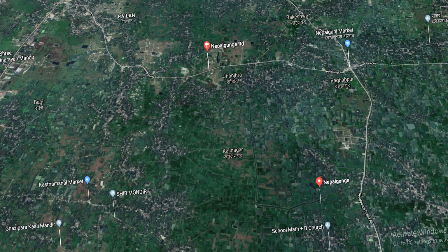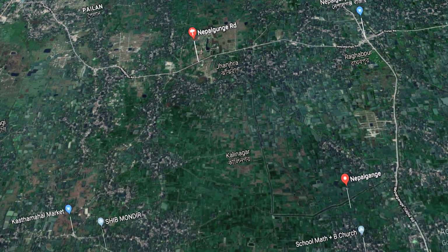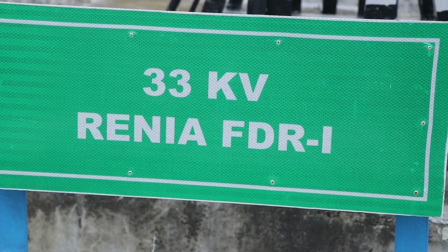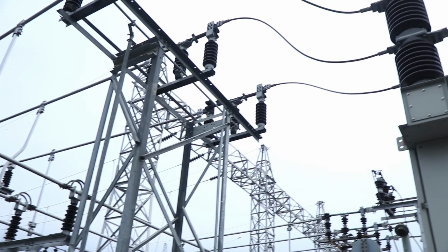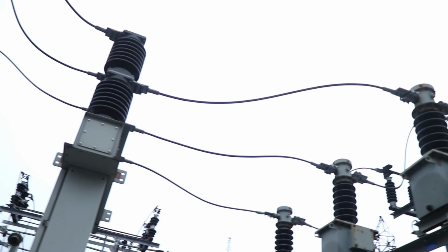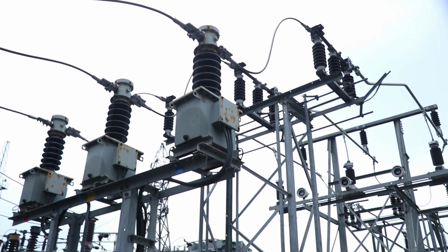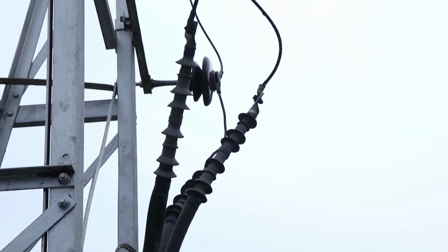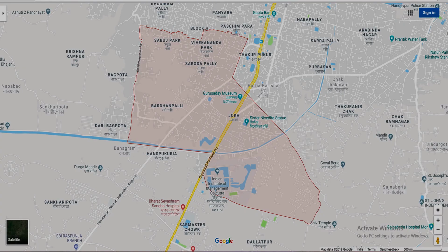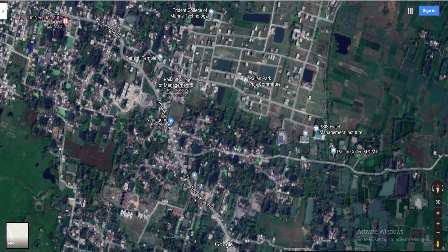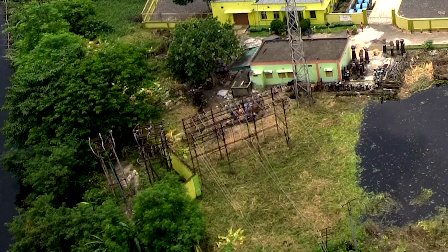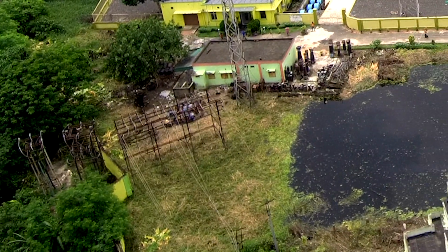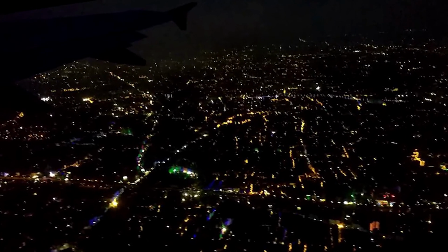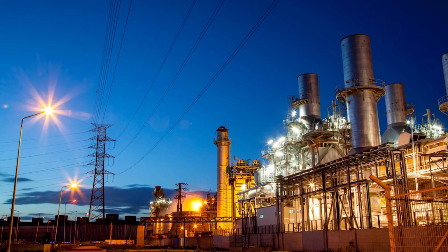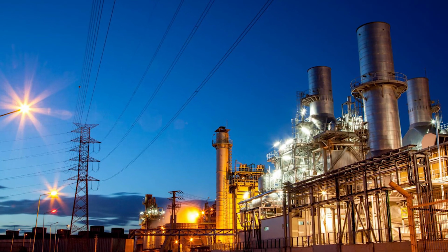It is giving power to suburban and village areas of Amtala, Rania, Nepalganj, Birlapur, etc. through 11 numbers of 33 kV feeders, and it gives power to nearby Joka, Pailan and Bakrahat areas through 7 numbers of 11 kV feeders. The substation is responsible for electrification of all domestic and industrial connections in this area.